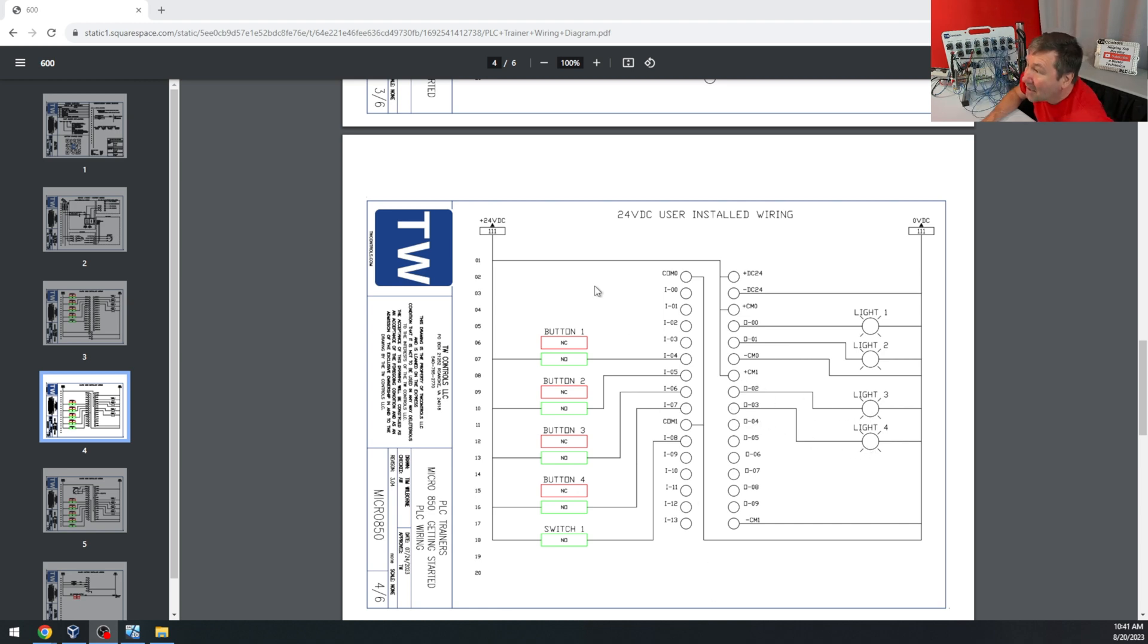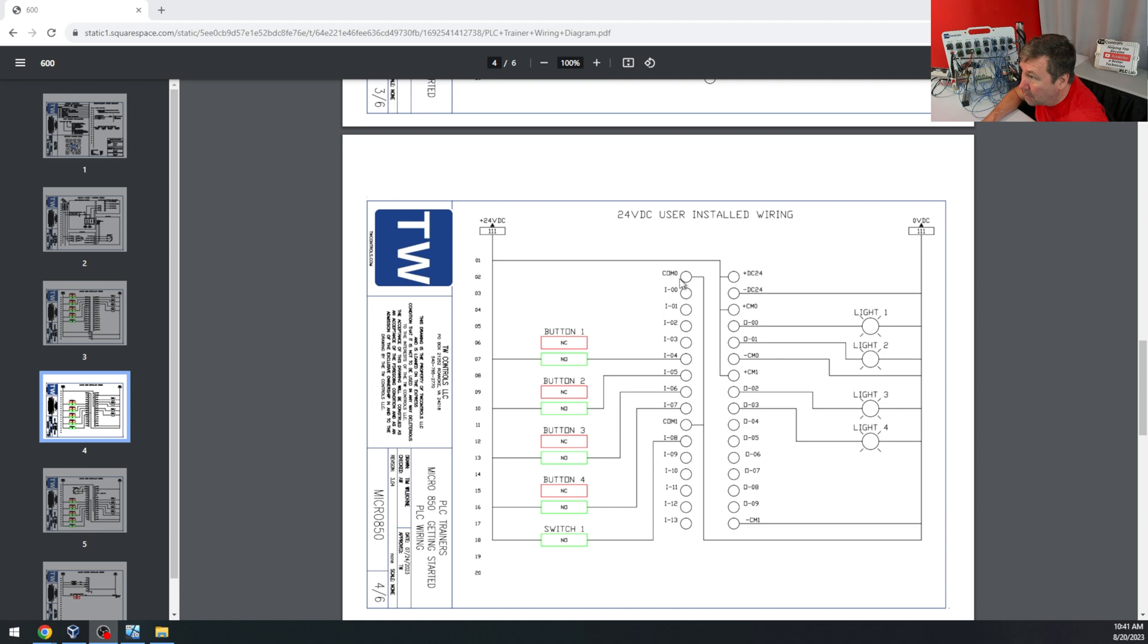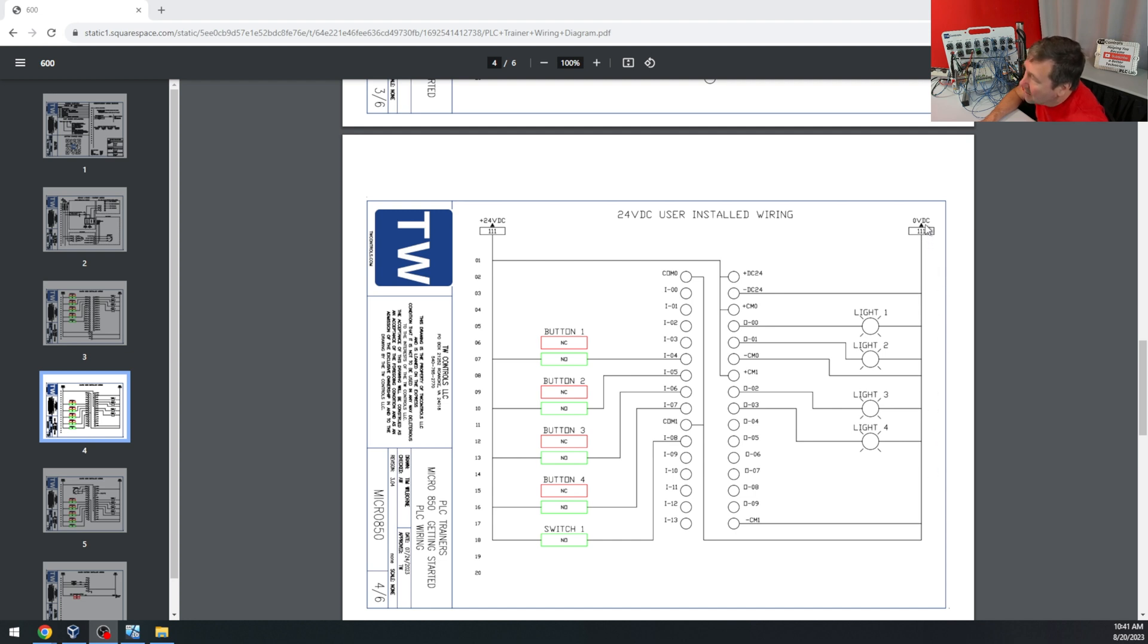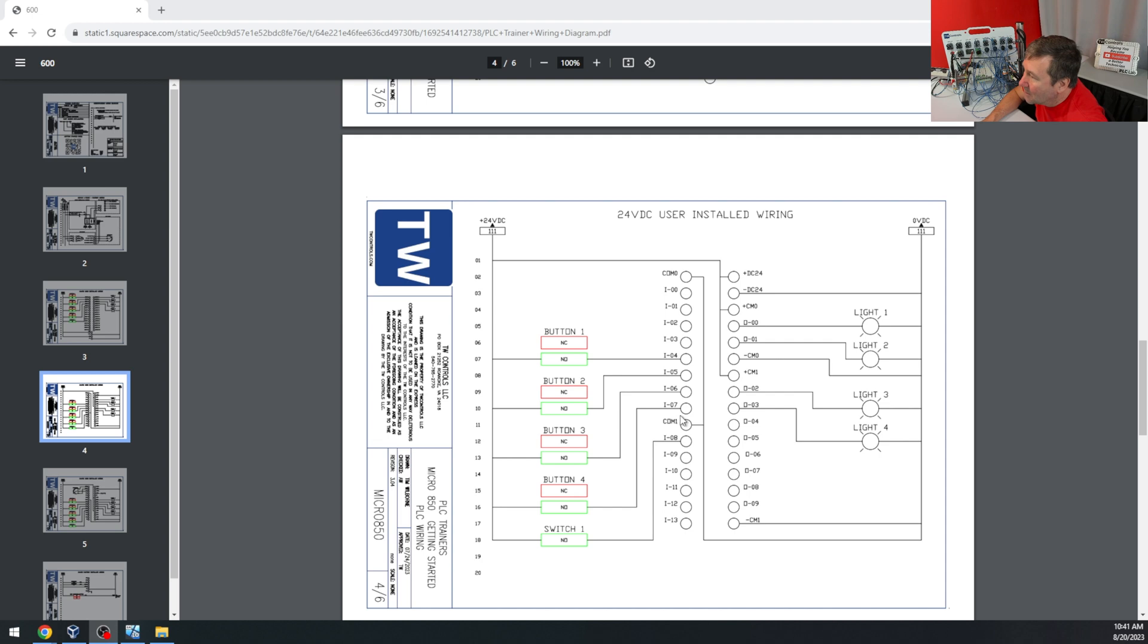Now we're going to connect the commons, which are the most common, no pun intended, issue that I see with people's field wiring. Let's start with the inputs. We're going to take COM 0 and COM 1 and connect them to the 0 VDC, and that is going to make our inputs sinking. And we have a video on sinking and sourcing inputs, and I'll put it at the end of this one.